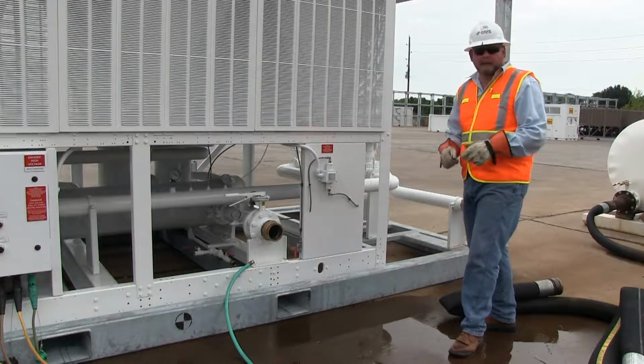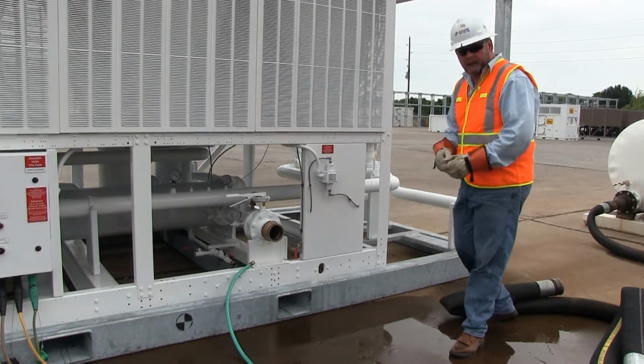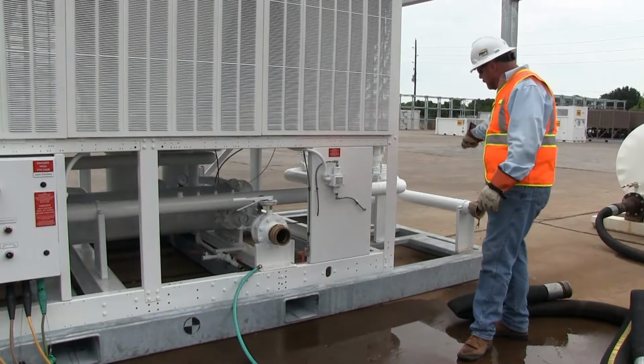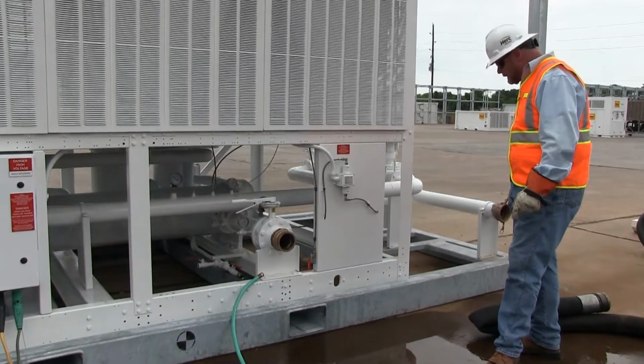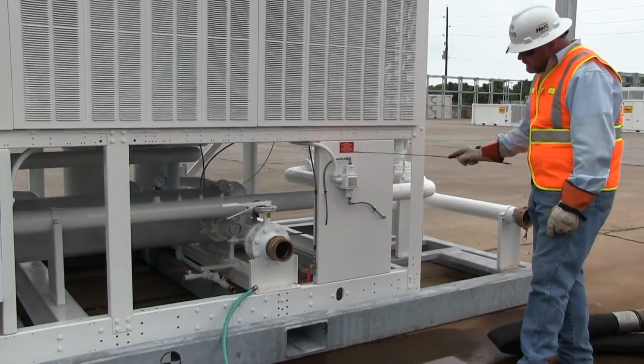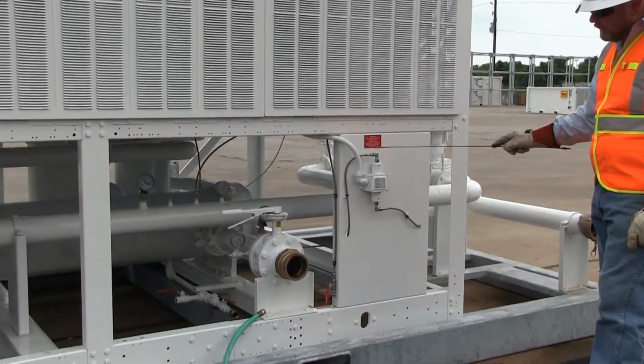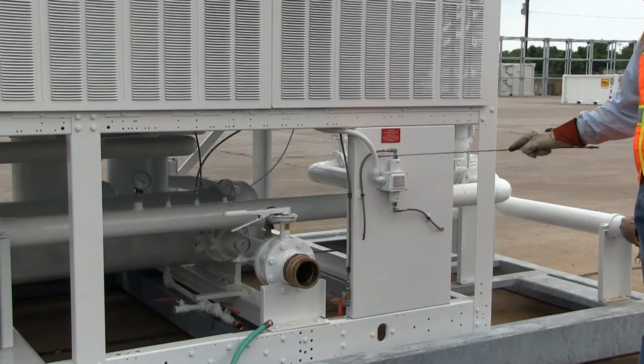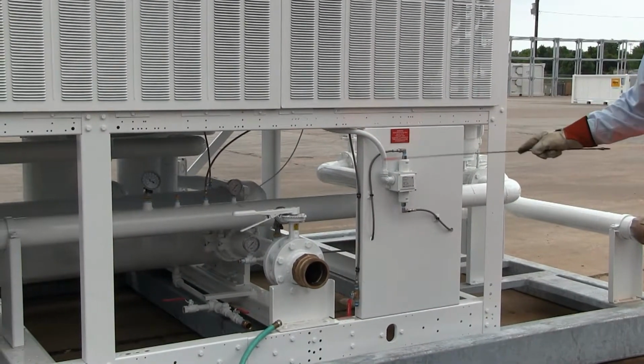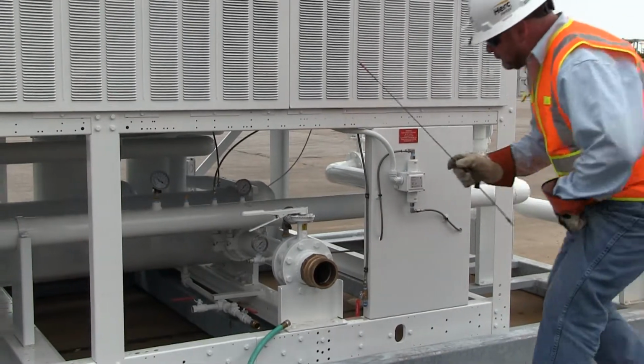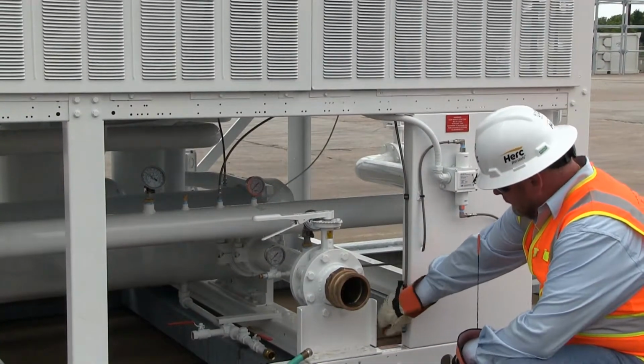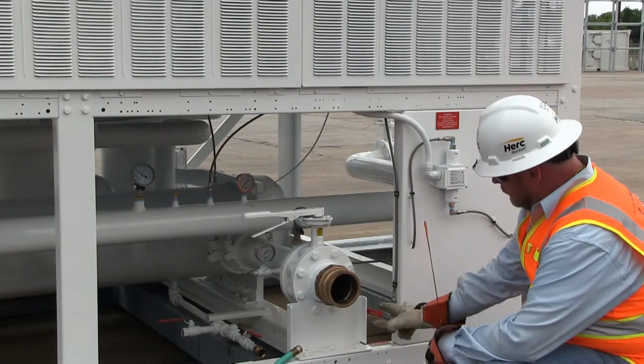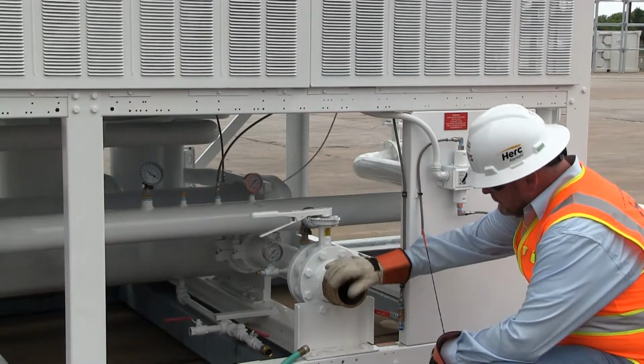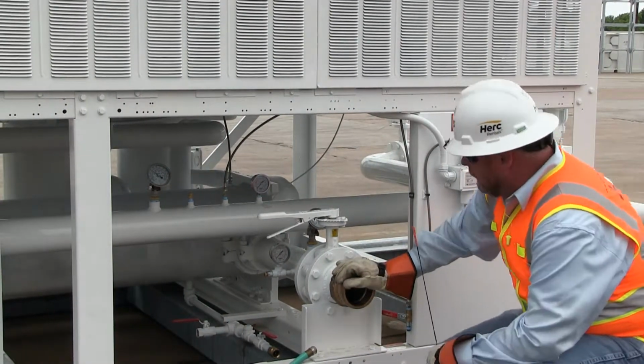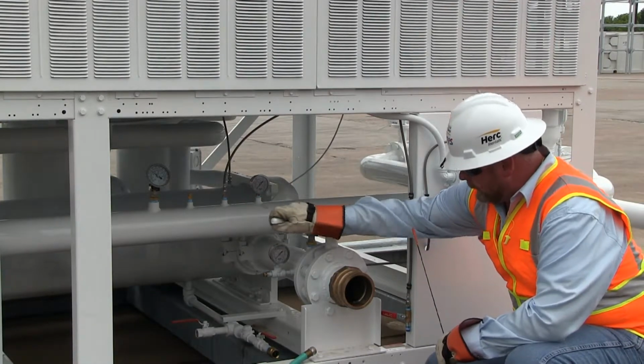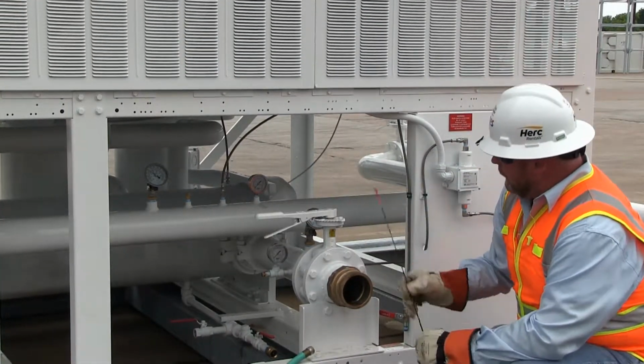Okay, let me go over some of the hydronic connections that we have, the water connections. The 4-inch inlet right here to our pump, which we just went through, 4-inch cam Dixon connection there. This is the differential pressure switch, better known as the flow switch. It measures the differential pressure between the heat exchanger and proves flow. As we go down here, this is the high point bleed. This is plumbed up to the top of the heat exchanger. This is how we're going to get our air out. This is the outlet right here coming off the chiller, and this is our balancing valve here that we open and close to regulate the flow.